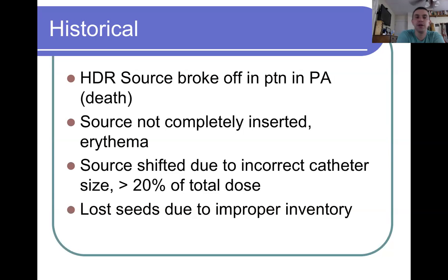So we have processes and policy in place that say the first person to enter after an HDR procedure should be holding a dose rate meter. We actually have fixed area meters on the walls with displays outside the vault. So even if you don't have a handheld, there's a permanent meter there that will let you know that the source has been retracted. And this is all to avoid a disaster scenario like that. And it should work. You can't be 100% confident in anything, but that's a pretty good way to know that the source will not leave that vault.